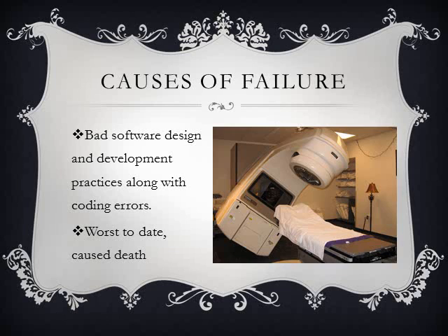The system noticed that something was wrong and halted the X-ray beam, but merely displayed a malfunction followed by a number from 1 to 64. The user manual did not explain or even address the error code, so the operator passed by and pressed the P key to override the warning and proceed anyway. The AECL personnel, as well as the machine operators, initially did not believe complaints. This was likely due to overconfidence.